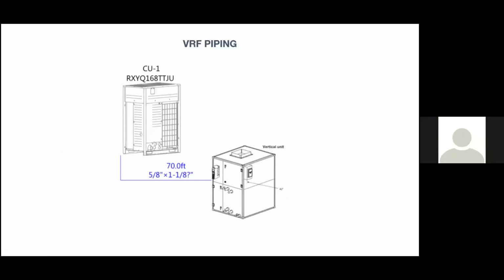So looking again here, this is a pretty typical VRF piping schematic that most manufacturers have out of their software, just showing the liquid and suction gas line from the condensing unit, which is labeled CU1 there, to the air handler in each space. So as I mentioned, you can see that the piping is 1 1/8 and 5/8. So pretty small pipes for these large capacity air handlers. As I mentioned, I think they were 12 to 14 tons, which is pretty easy.